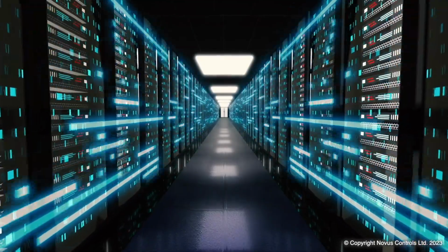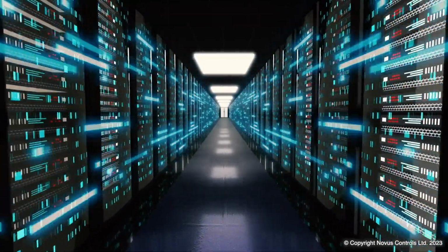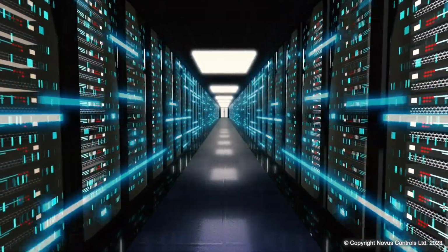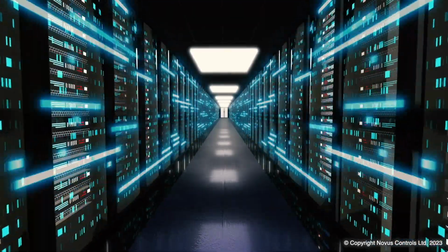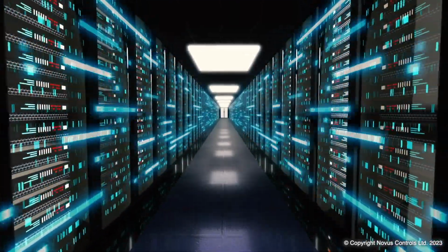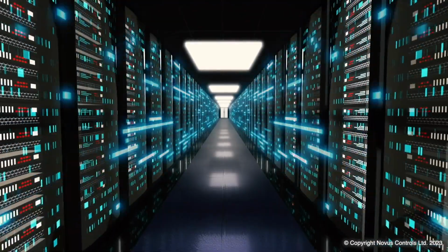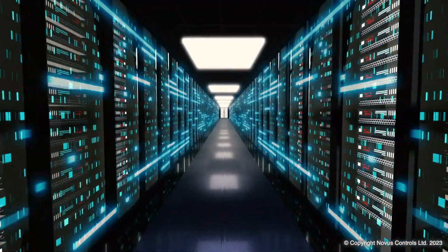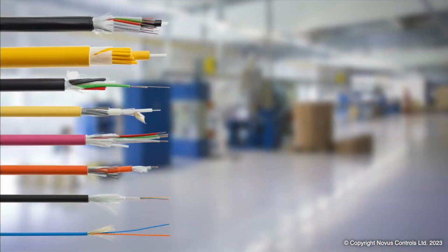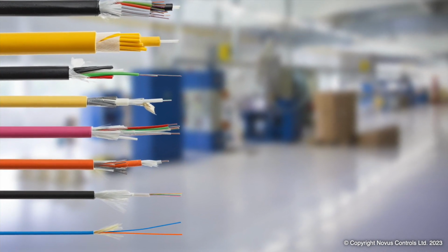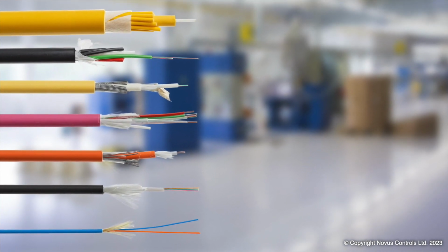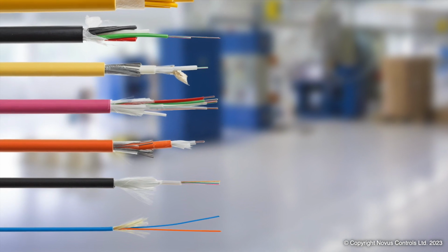Fibre cables have the ability for increased bandwidth in a like-for-like size of cable when compared to a copper equivalent. Because the cores of the fibre cables are small and the majority of the cable diameter is due to the protective layers, increasing the number of cores does not significantly increase the overall diameter of the cable. The difference in size between a 4-core and an 8-core fibre cable is minimal.